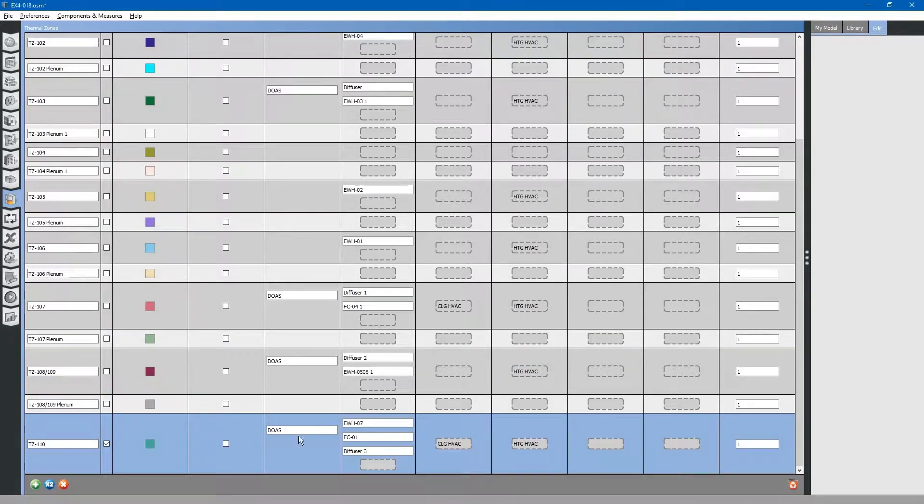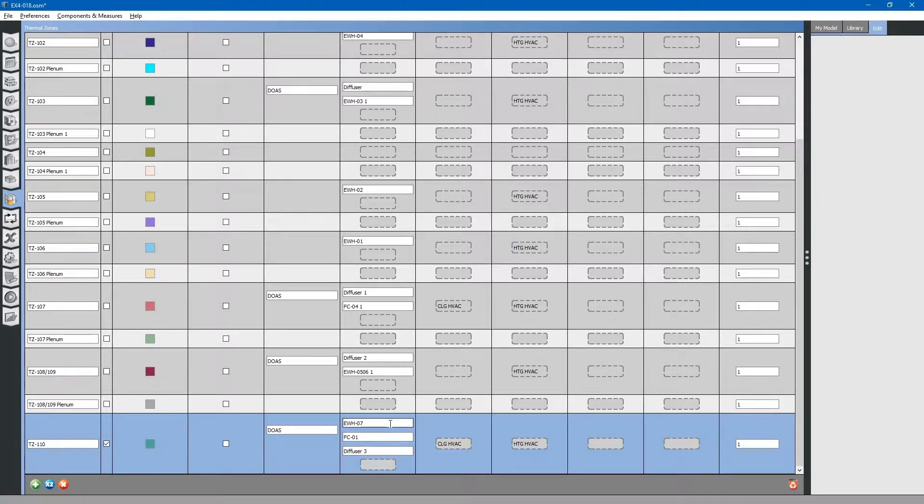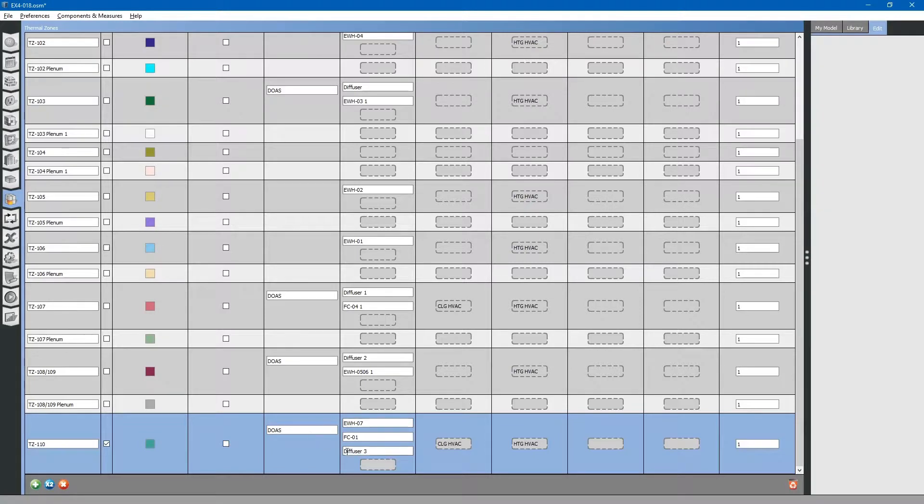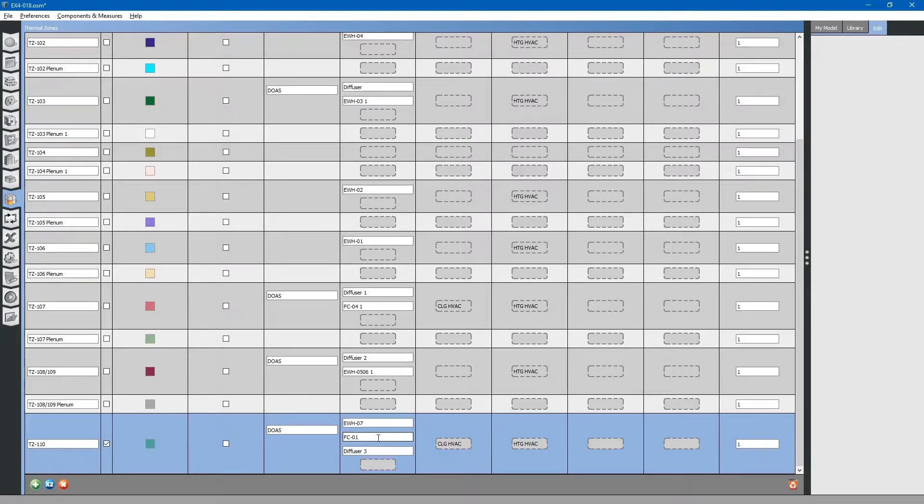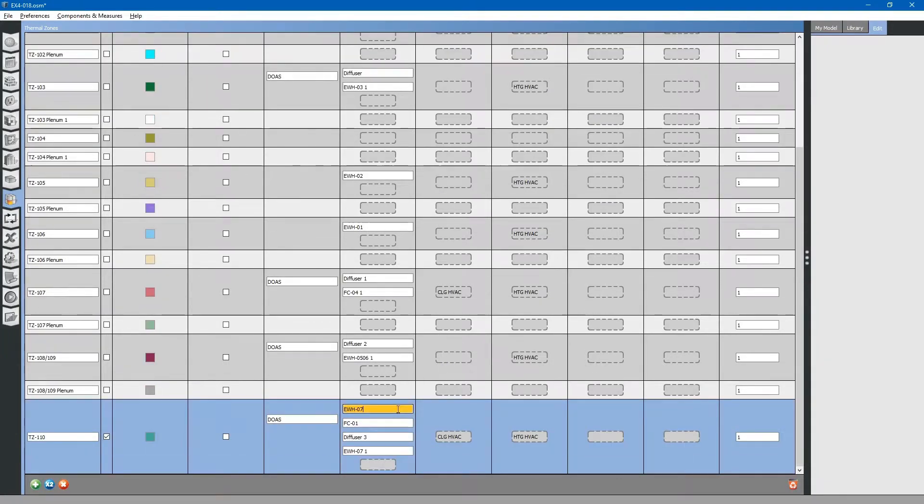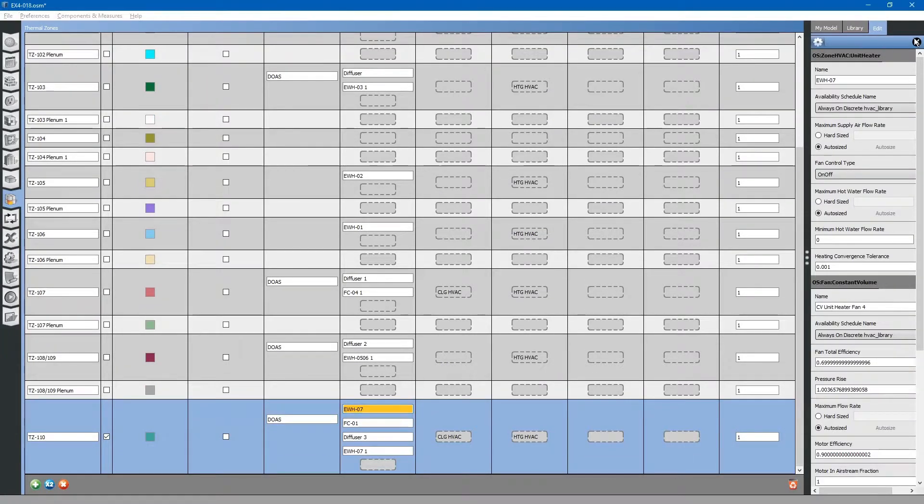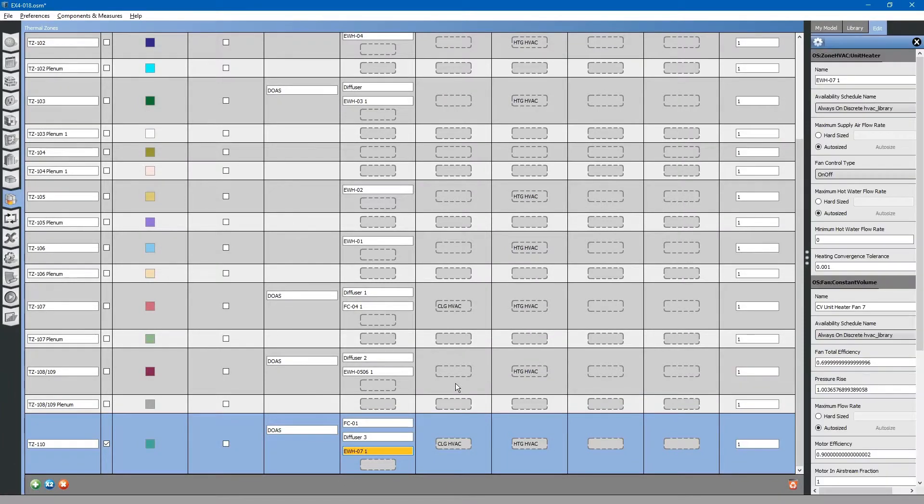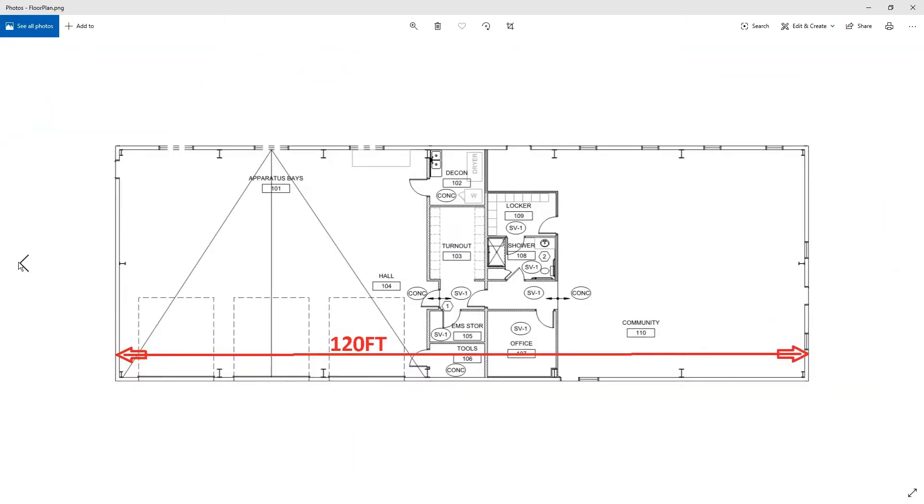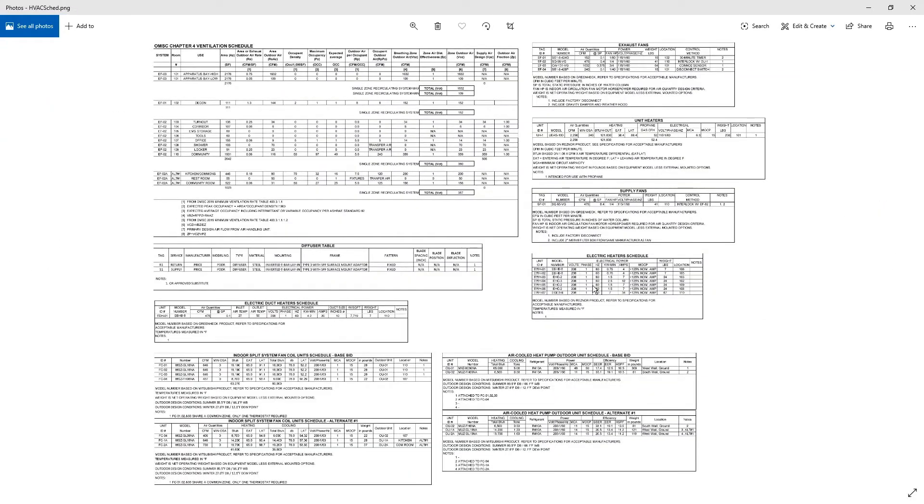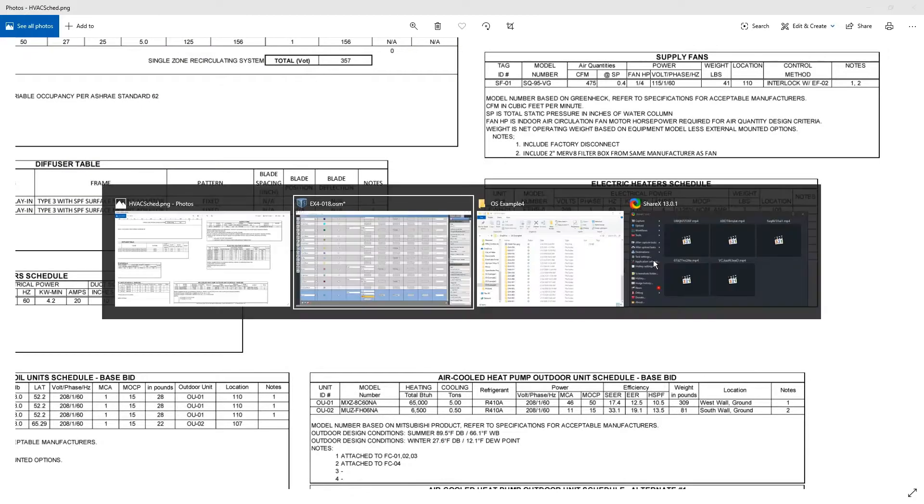For thermal zone 110, it is a little bit trickier. We have several pieces of equipment here. Because we have so much equipment, we need to hard-size one of these pieces of equipment. For example, we want the dedicated outdoor air system to supply heating primarily. Next, the electric wall heater will come on to supply additional heat. Finally, the split system package terminal unit will supply the rest of the additional heat needed. We need to do the wall heater first. We will hard-size the wall heater to seven kilowatts.